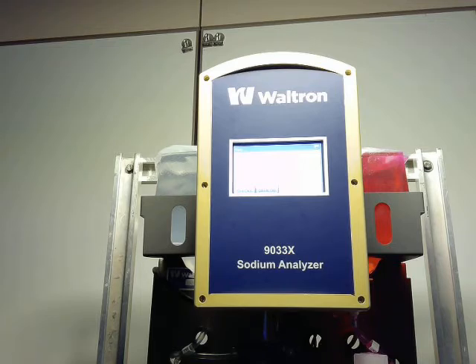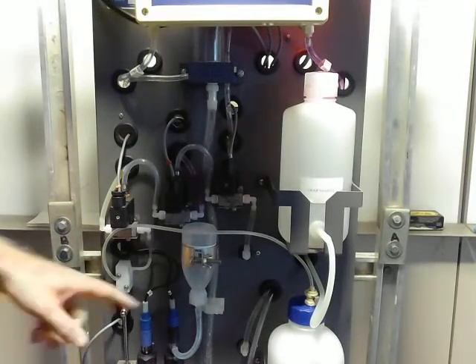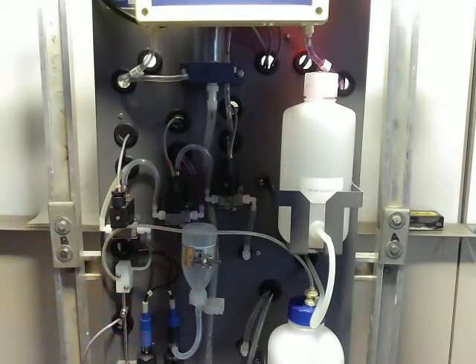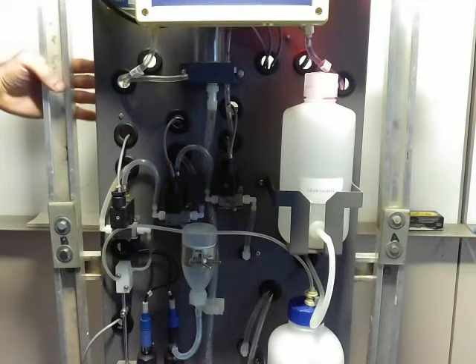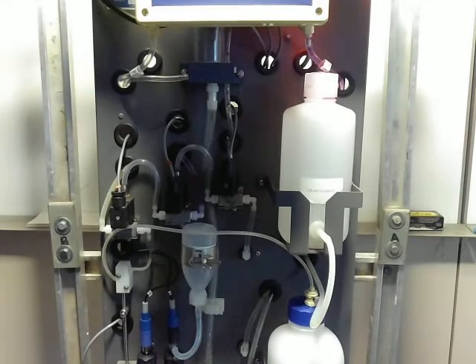So the probes are connected through the cables. Your reference and your measuring probe both have a grounding side and their measurement side, and they connect into the preamplifier, which is behind this wet section panel, before it goes to the transmitter, and it's grounded inside the preamp, to ground out the signal between the electrodes.